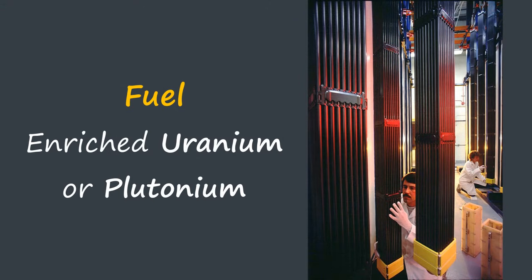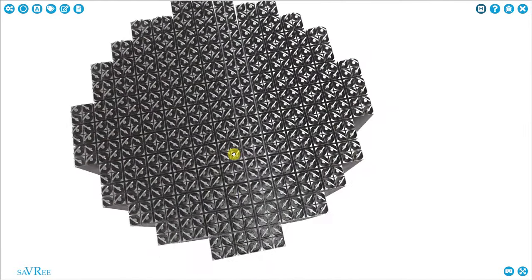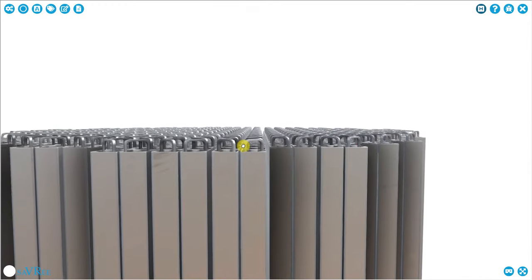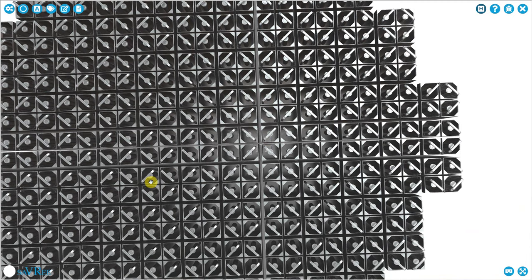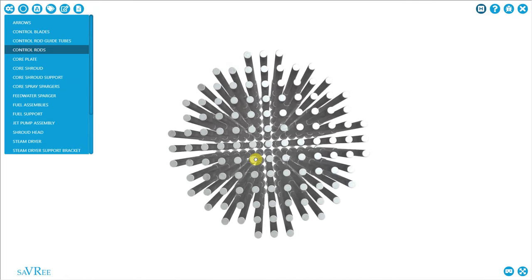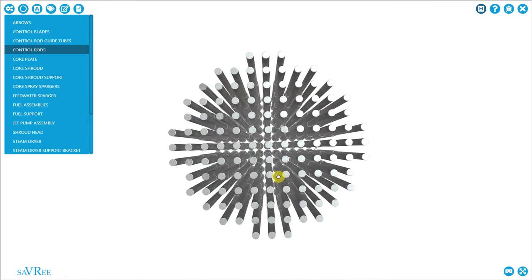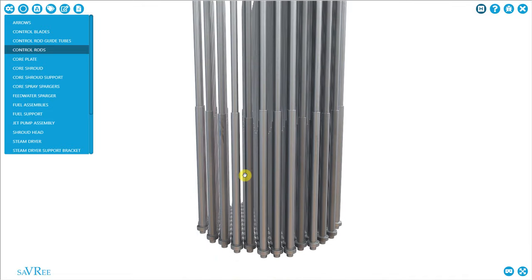And the water will flow upwards through our fuel assemblies. A fuel assembly is represented by long, thin fuel rods. And it's within this space where the fuel assemblies are that our water will be heated. You can see them here. These are our fuel assemblies. We've actually got handles on the top because we remove the vessel head in order to get to the fuel assemblies, to pull them out and change them, maybe every 18 to 24 months, depending upon design. Between each of the fuel assemblies, we will have control rods scattered around. You can see they're here. They're laid out in a pattern between the fuel assemblies so that when we insert those control rods, we can slow down the rate of reaction and thus reduce our megawatt power output.